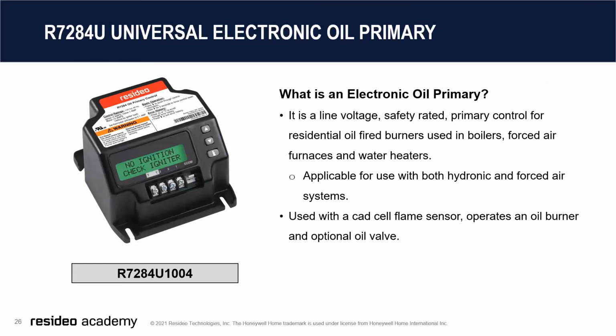The R7284 Universal Electronic Oil Primary. What is an electronic oil primary? It's a line voltage safety rated primary control for residential oil-fired burners used in boilers, forced air furnaces, and water heaters. Works great in both hydronic and forced air systems. The use of the CAD cell flame sensor. It's going to operate your oil burner and optional oil valve.